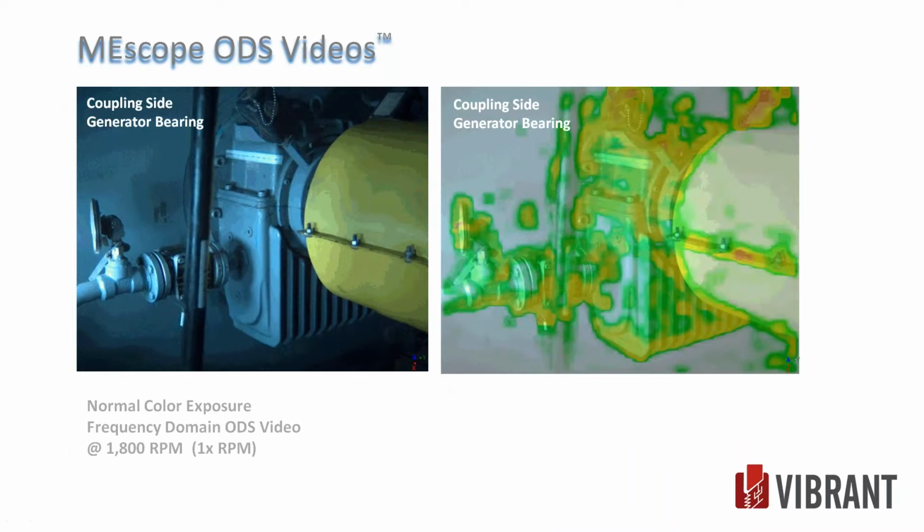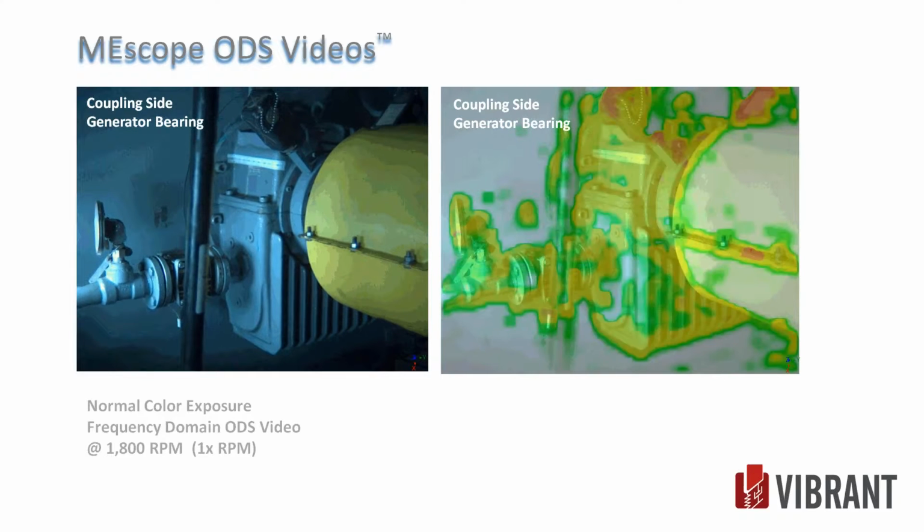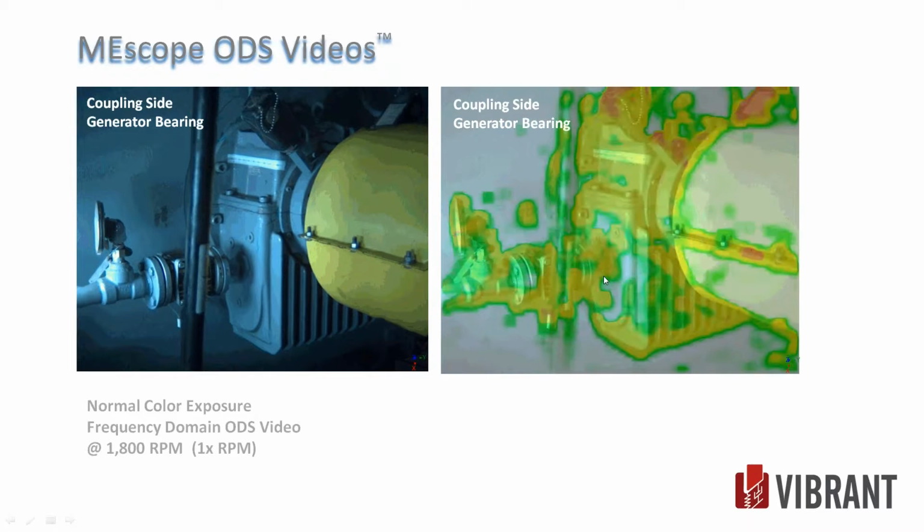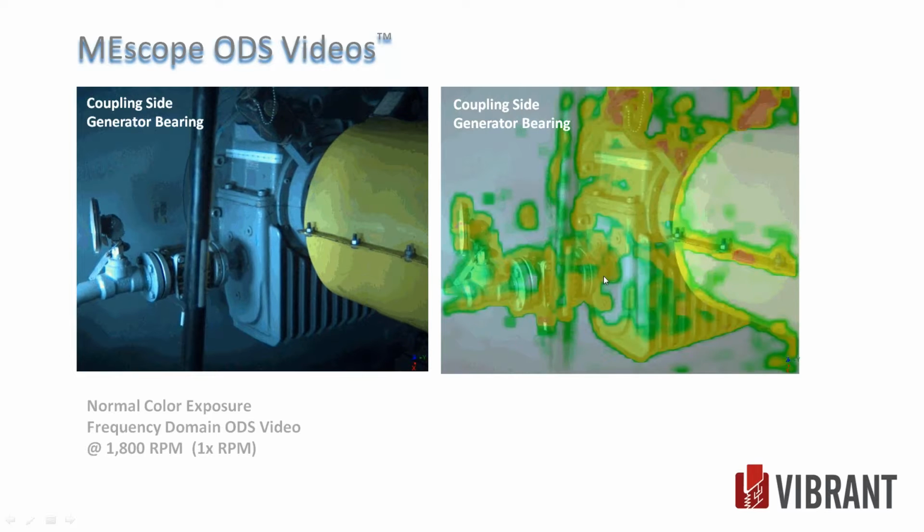Another picture of the coupling side generator bearing, and its color contour response. Everything's in phase, vertical and thrusting motion.